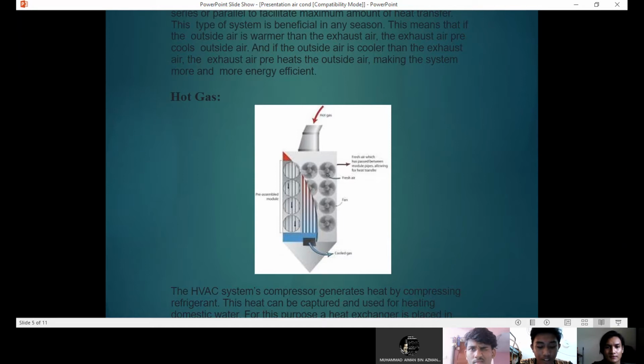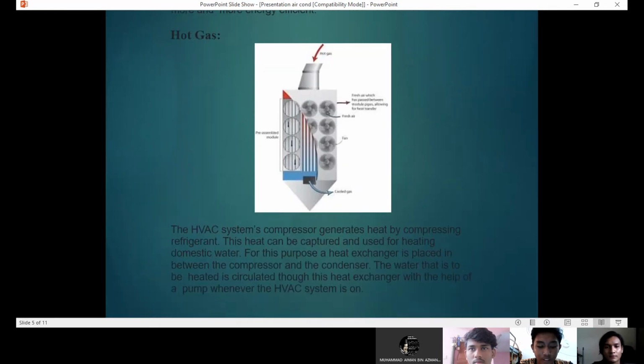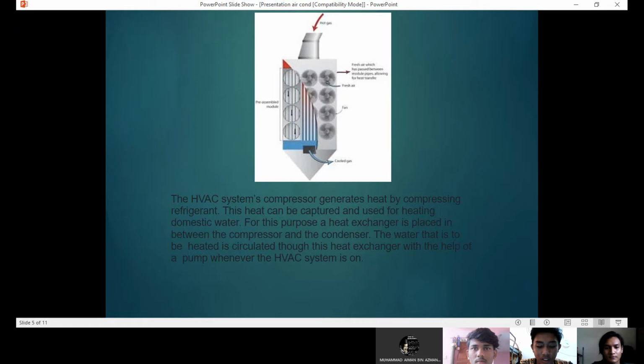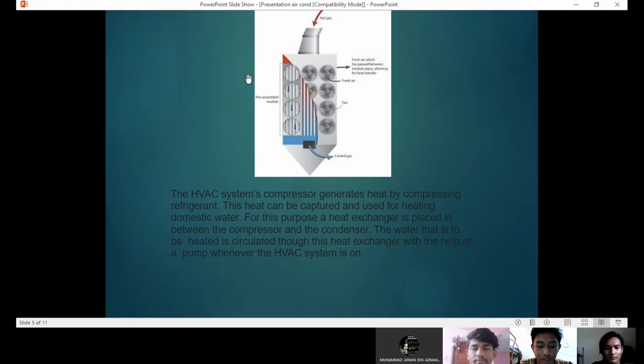Seterusnya, hot gas. The HVAC system compressor generates heat by compressing refrigerant. This heat can be captured and used for heating domestic water. For this purpose, a heat exchanger is placed in between the compressor and the condenser. The water that is to be heated circulates through the heat exchanger with the help of a pump whenever the HVAC system is on.